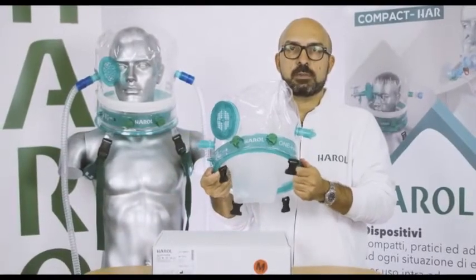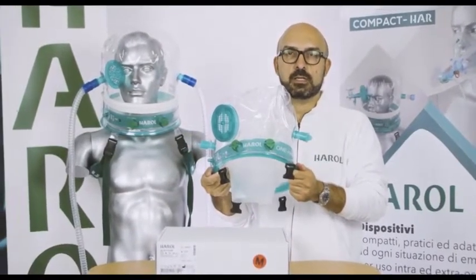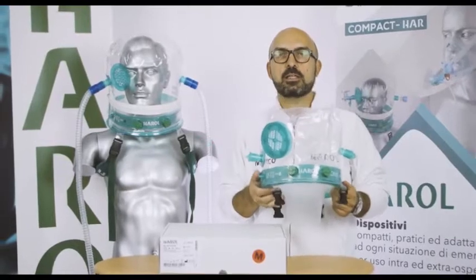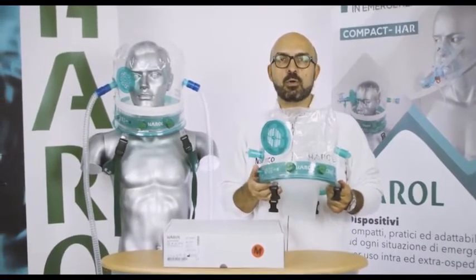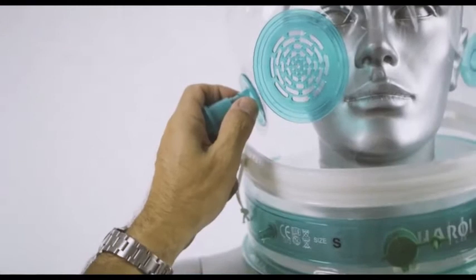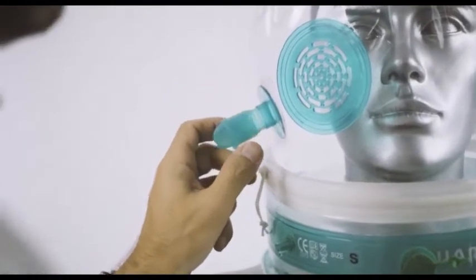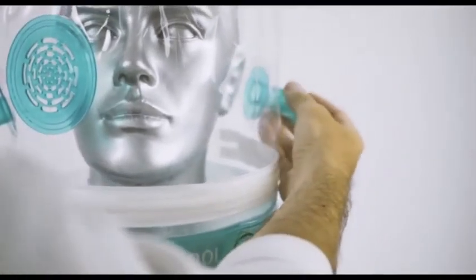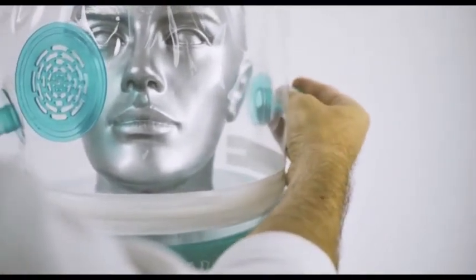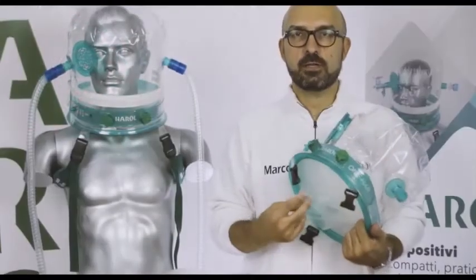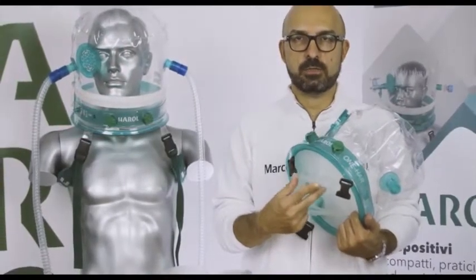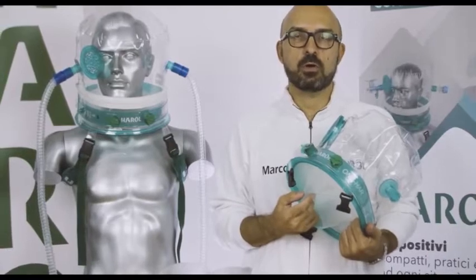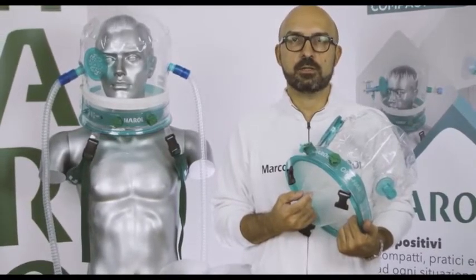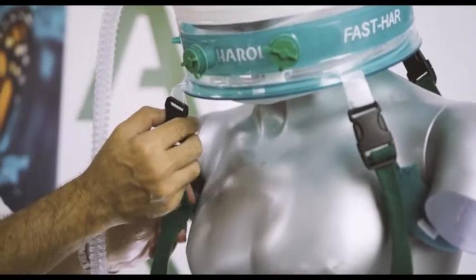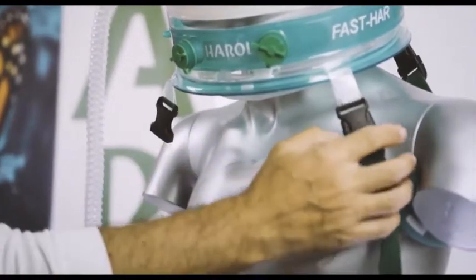The helmet is equipped with a rigid ring to maintain the shape during the therapy. Weight is approximately 320 grams or 400 grams based on the model. The seal of the helmet is guaranteed by a soft and elastic silicone collar. It seals over the neck, so it is not necessary to pull too much the suspenders to guarantee a good tightness and synchronism with the ventilator.